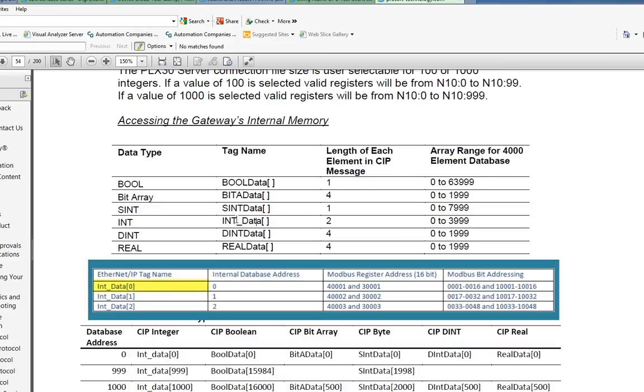If we review this simple chart, you see that int data zero corresponds to the very first register in the gateway's internal database. It is also the first Modbus register.